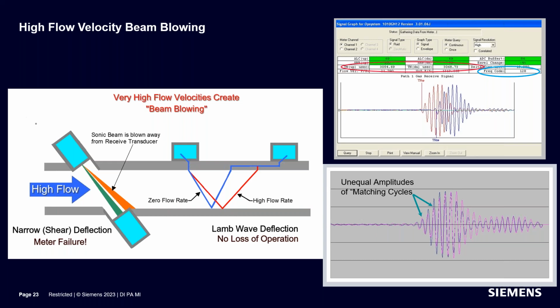And we apply a correction factor for it, and that eliminates errors that are potentially caused by a beam blowing condition. This is a user-initiated automatic correction for the change that occurs in the signal created by beam blowing. It's a very simple function. The user just goes to the menu location, selects enable for the beam blowing correction, or the HF, and says do it, more or less. It just says activate. The meter does the calculation and sets the correction factor automatically.